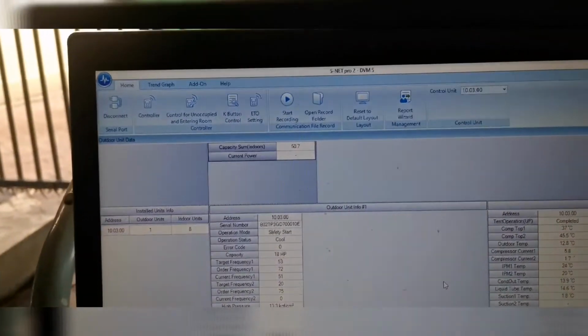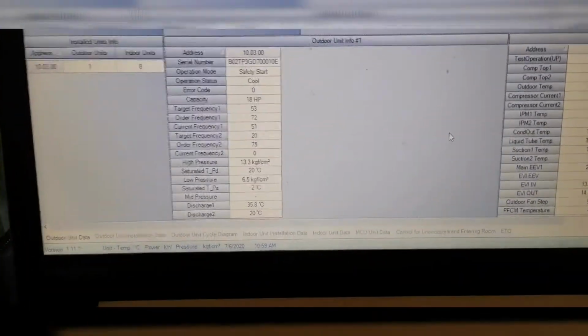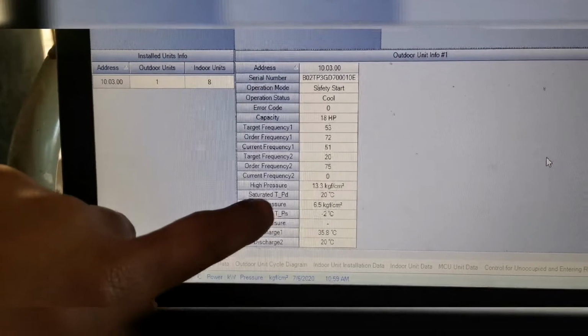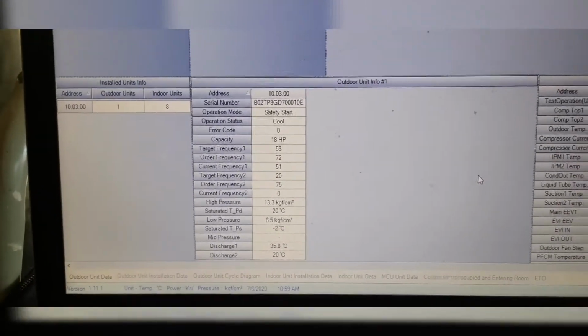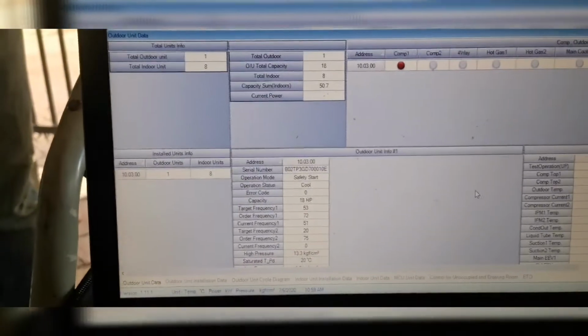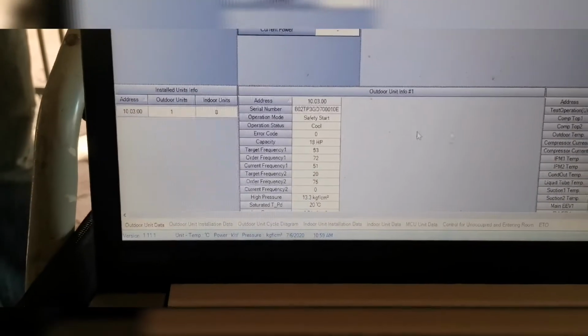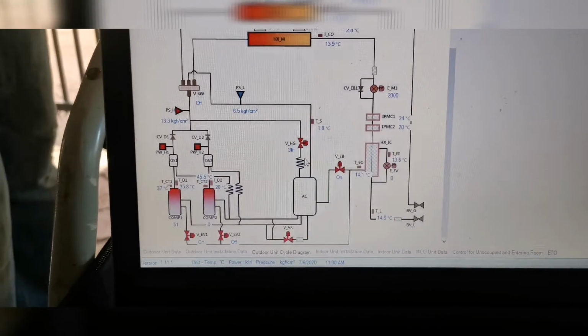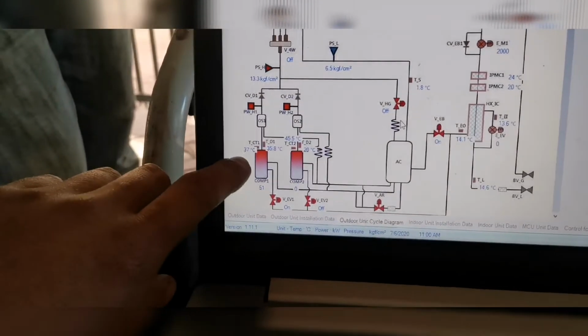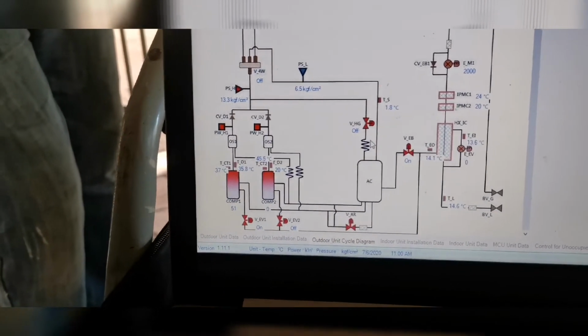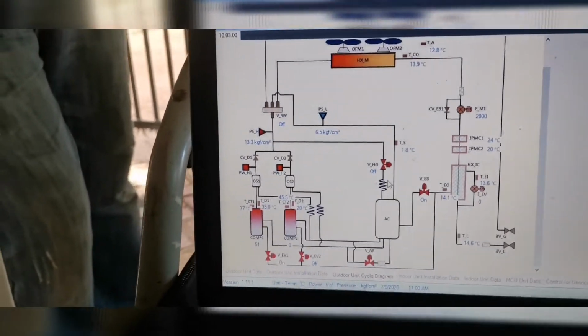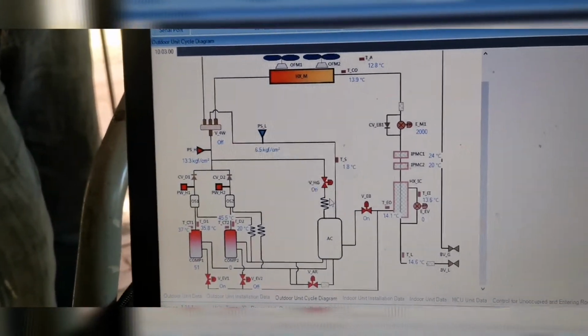So just off the bat, we know we're a little bit low, so we're gonna add additional charge to the system. The base charge is 8.4 kilograms and the additional charge is 18.8. So we just need to add a few more kgs, and you can see these saturated temperatures right here are calculated, so that's not measured by a physical sensor. So I'm not too worried about that. Like I said, we're going to give the system 15 minutes to stabilize before we start looking at the numbers. So this is just a diagram of the entire outdoor section. We can see compressor 1 is running, compressor 2 is still off. Now the pressures are quite low at this stage, but I'm not worried about that. We just started up the unit, so let's give it 15 minutes and I'll get back to you guys. Cool.